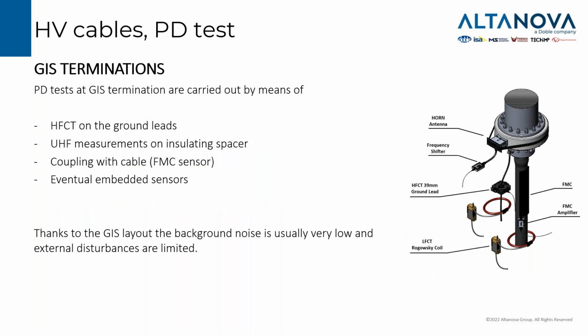A brief introduction of which sensors we can use in GIS terminations. We can use a high frequency current transformer on the ground leads. We can use UHF antennas on the insulating ring spacers of the termination, and take a look also at the upper portion of the termination that connects the GIS to the cable. We can use an FMC (flexible magnetic coupling) sensor along the cable, and eventually some of these accessories have their own partial discharge sensor embedded, and we can take advantage of this sensor to perform a very sensitive measurement. An advantage of testing the GIS is that the background noise is normally very low, and we do not have, in the case of a GIS substation, all the external disturbances related to outdoor high voltage assets.